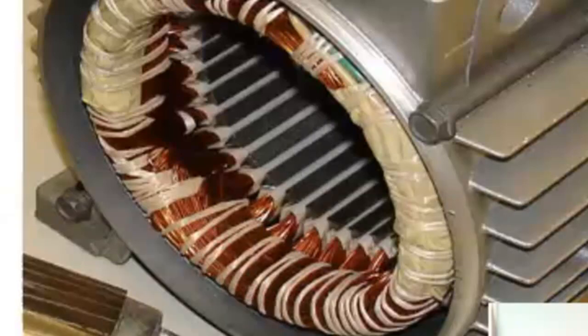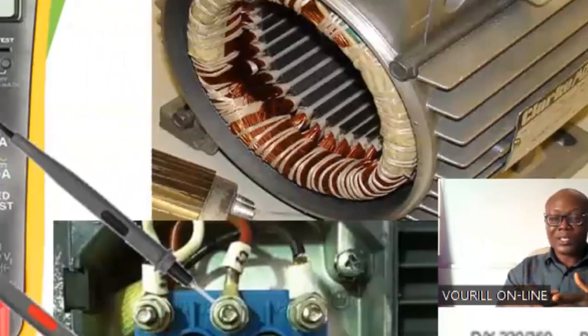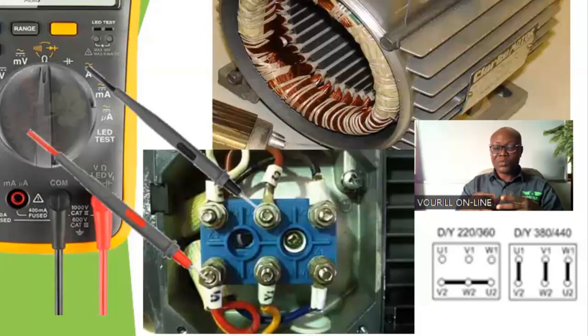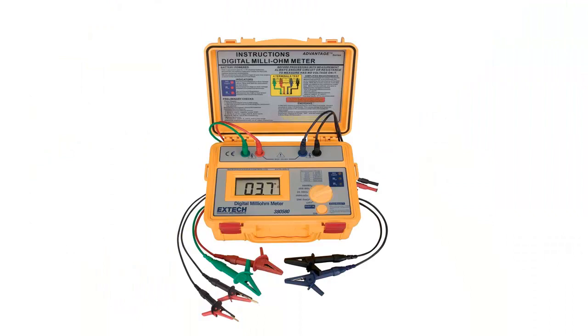But once those windings are burnt, it means that at that point of burn, the windings may have been shorted at that end, or it may open up the circuit. Whatever the case, if it opens up the circuit, probably the heat was not strong enough to break the insulation between the winding and the yoke. So you will not get a winding to ground reading because of that. But you can carry out resistance tests.